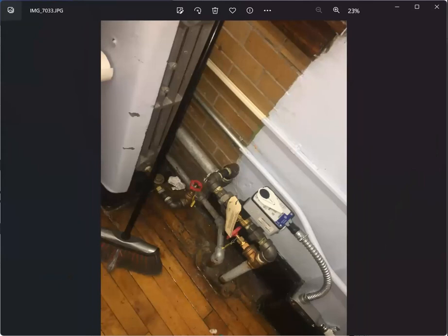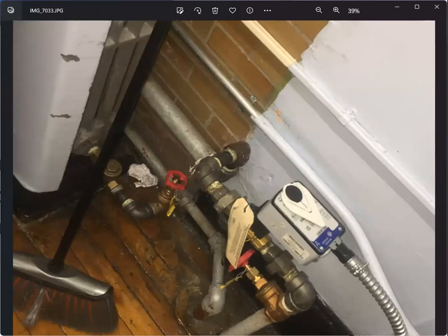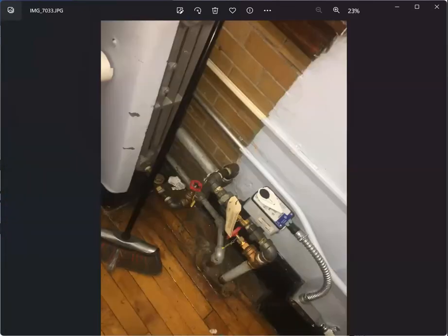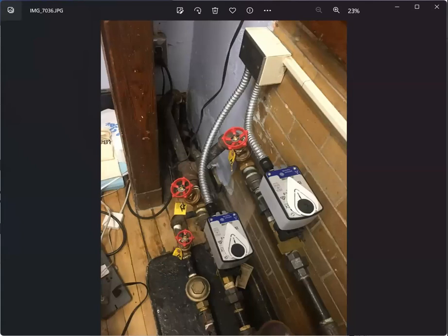The use of it is that if you identify the model number, sometimes it's not gonna match the drawing specification or the design. It takes long before it gets to be constructed. So some of the specs on the drawing weren't updated, or they're still gonna update it just to start the work. They're gonna go over it and probably just provide an approved submittal supporting document for each equipment and device.